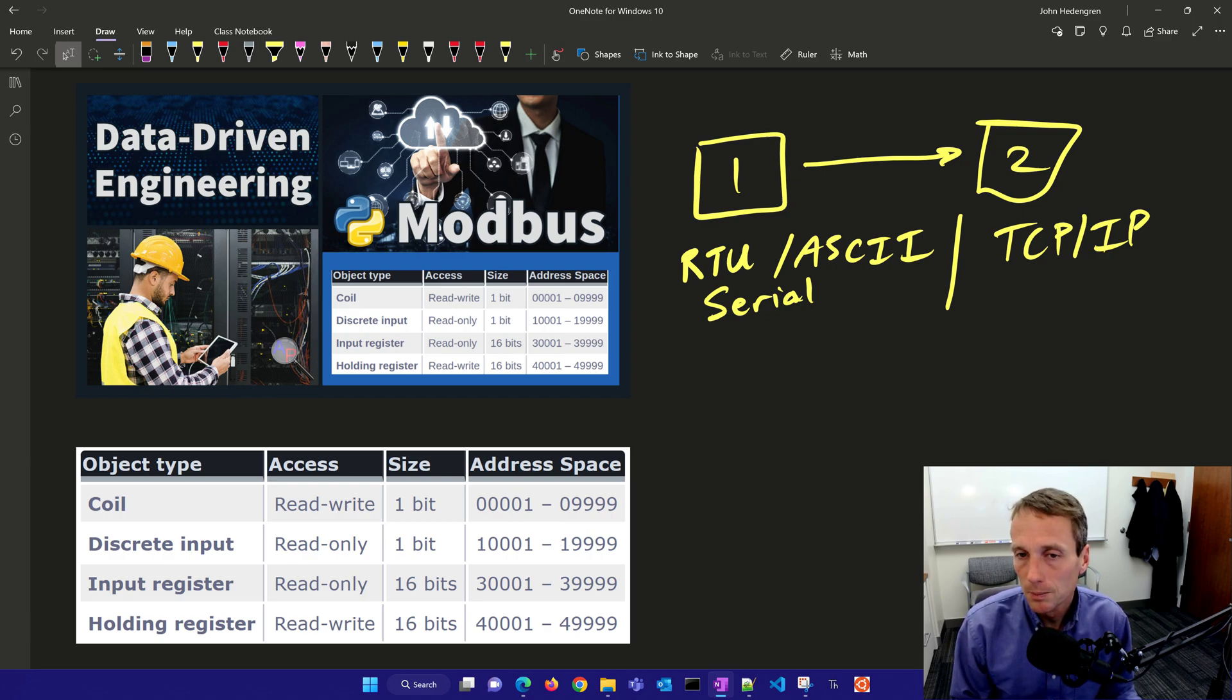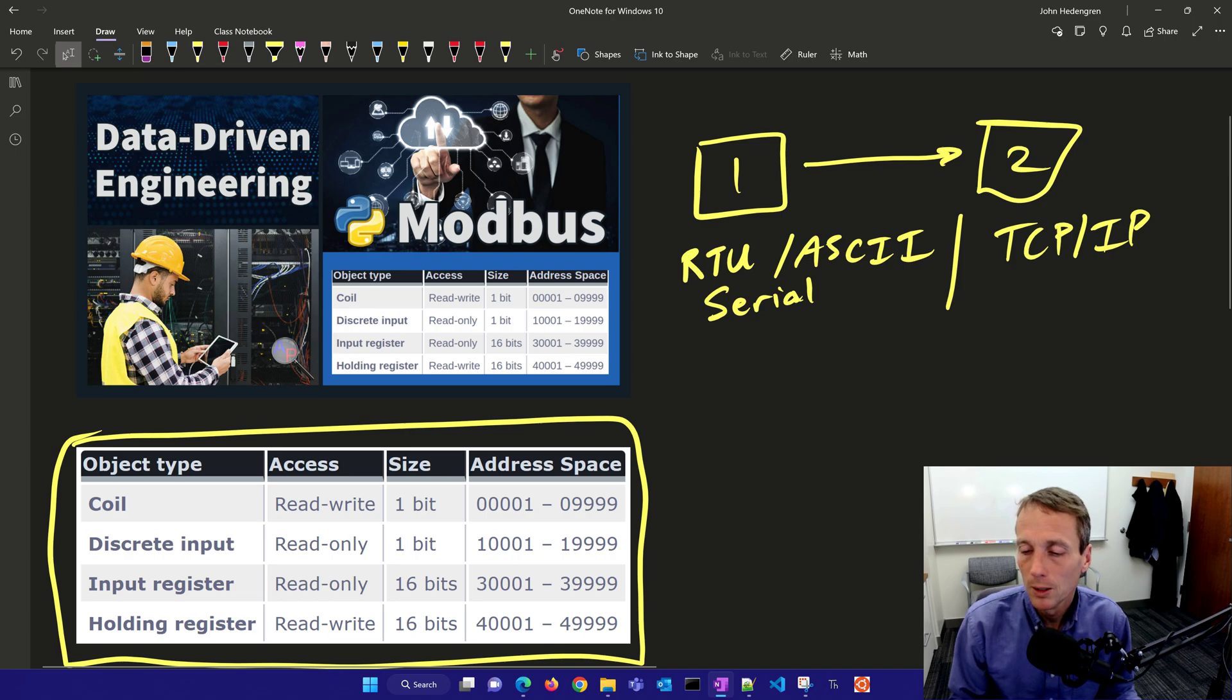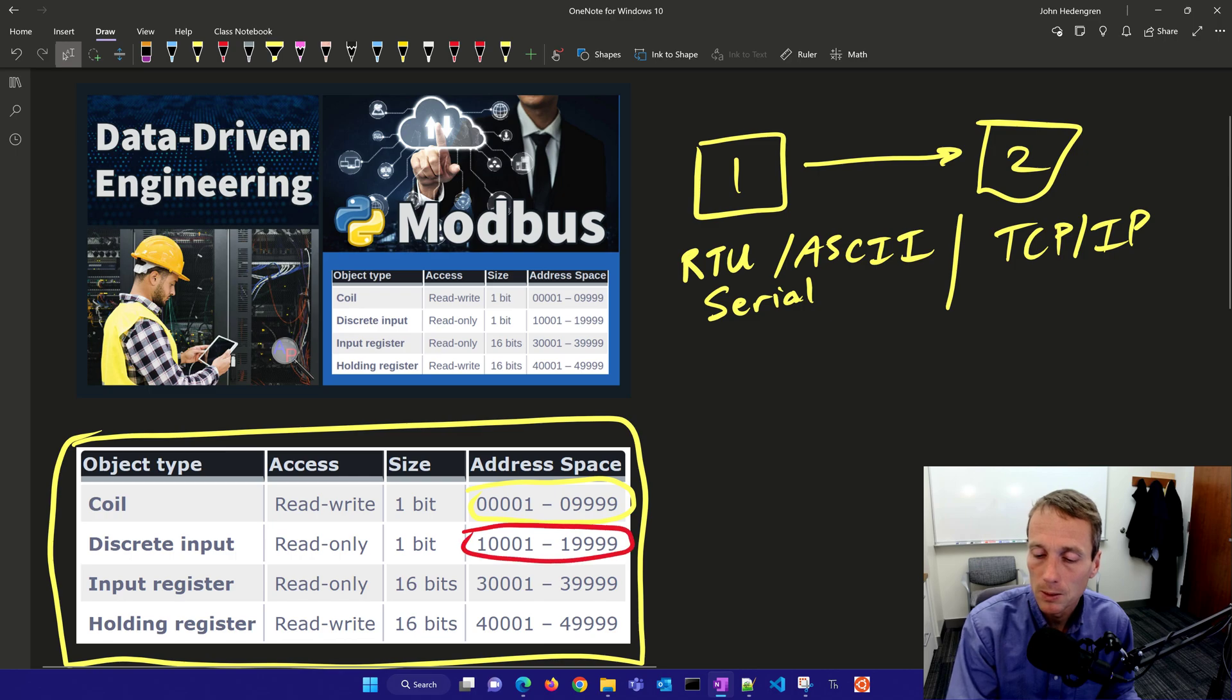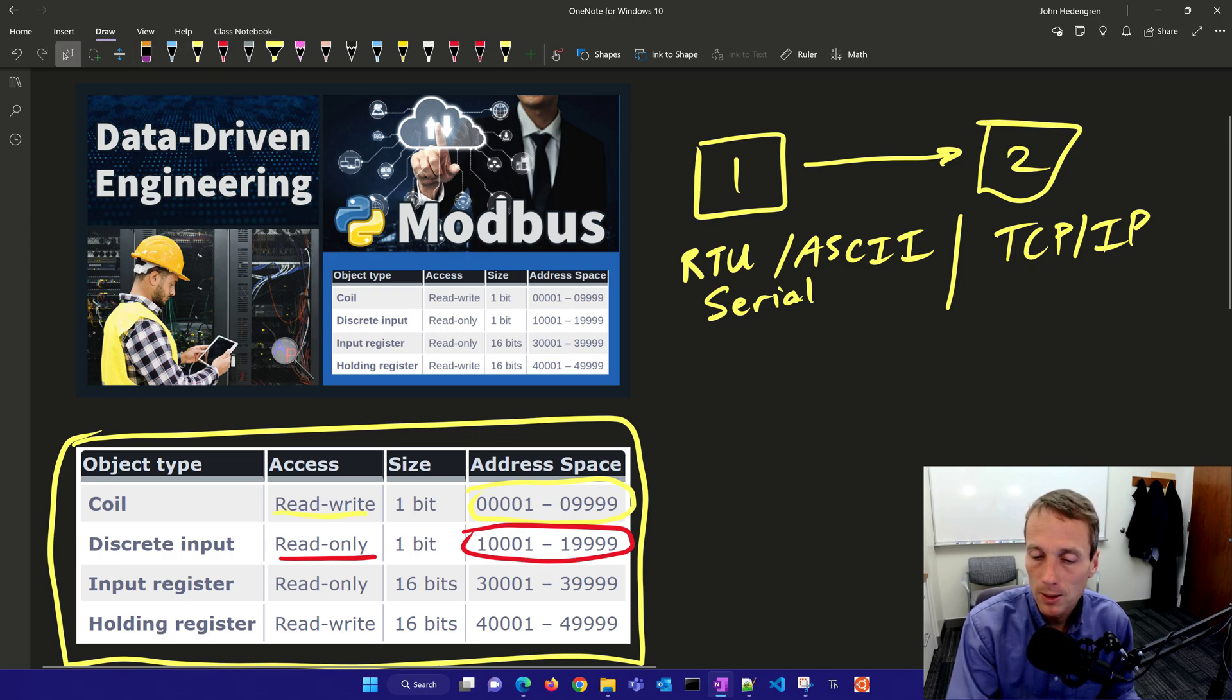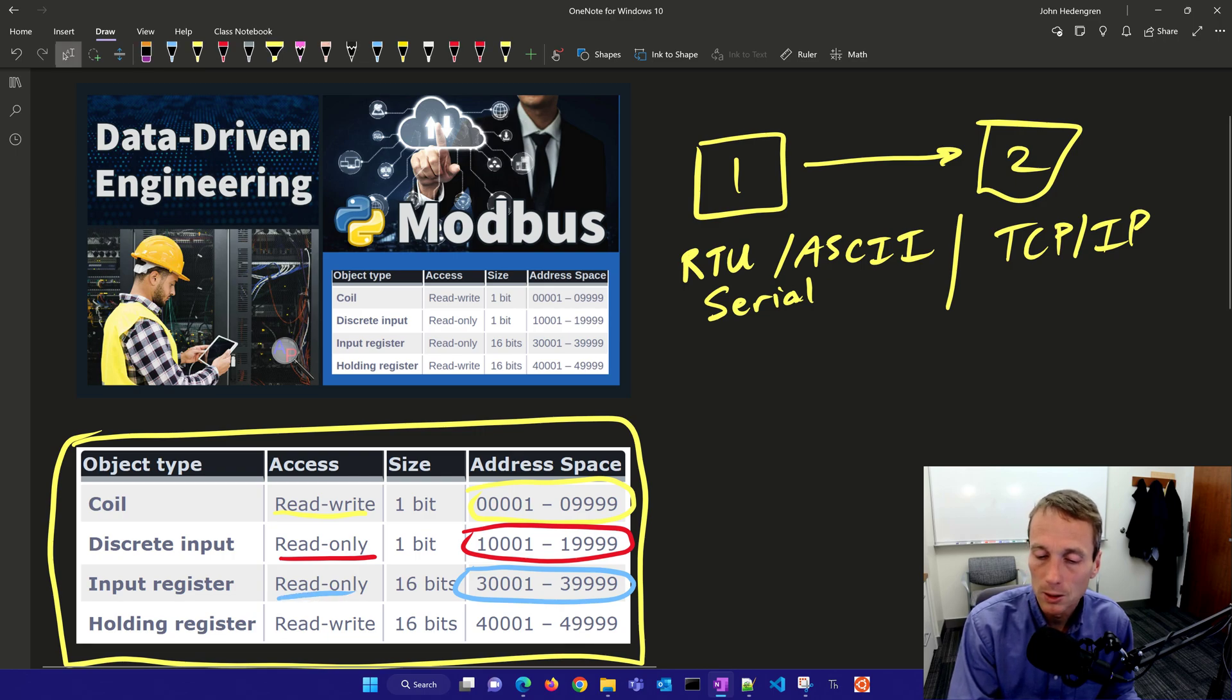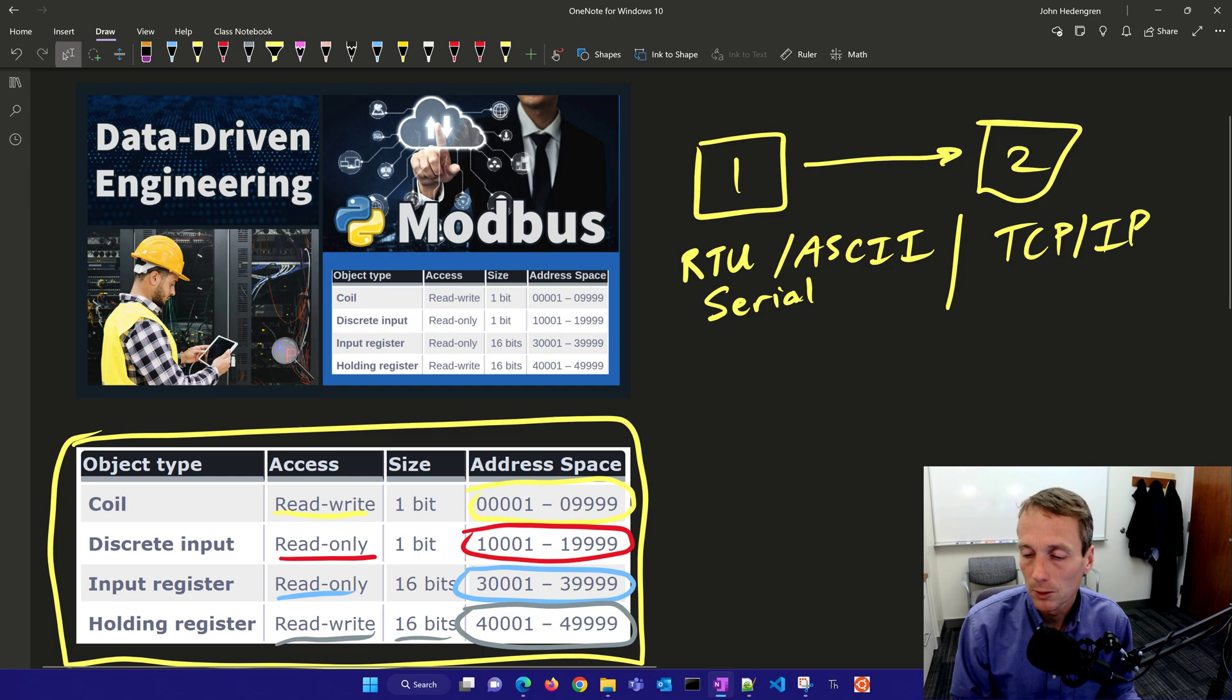In Modbus we have a couple different address spaces set up by the protocol. Coils are single bits, read-write. Discrete inputs are read-only. Then as we look at another address space, the input registers, those are 30,001 to almost 40,000 and those are read-only as well. The ones I typically use for most applications are the holding registers where you could transfer 16-bit numbers over to another computer.